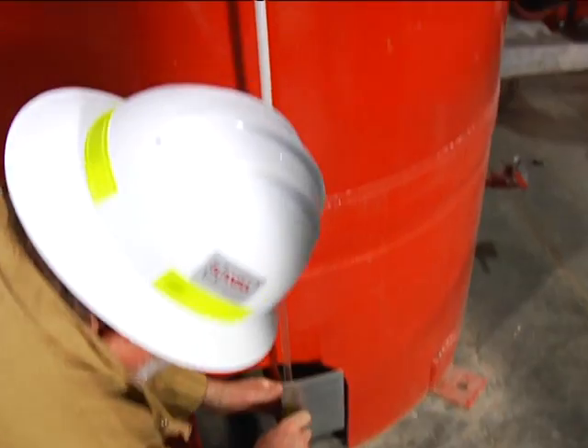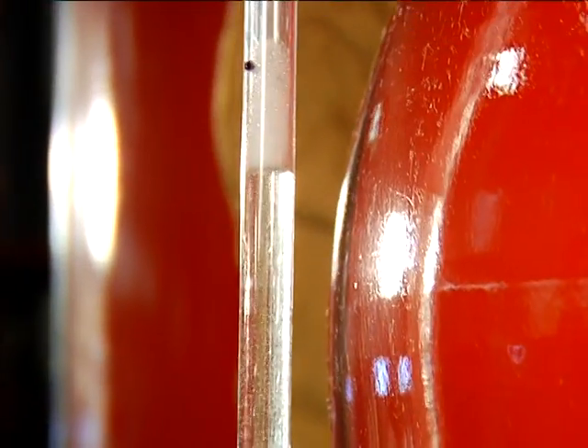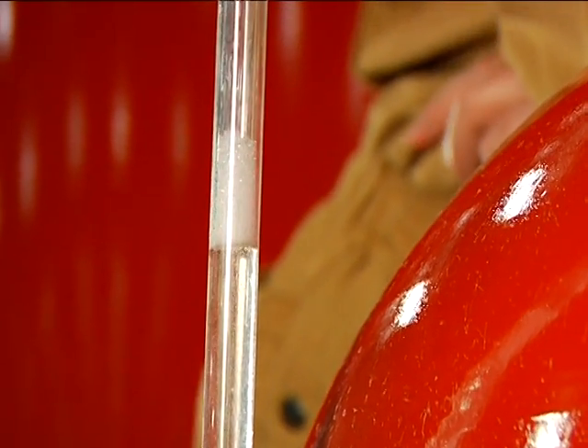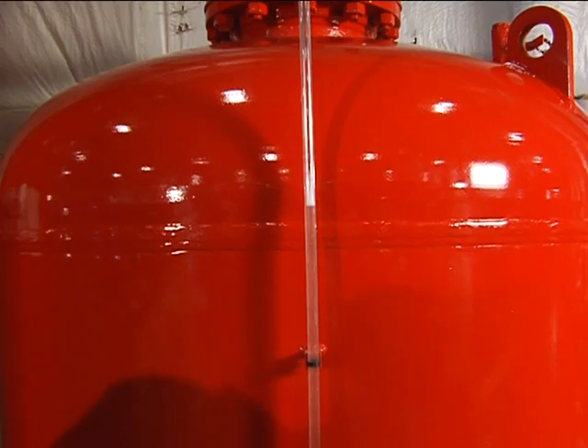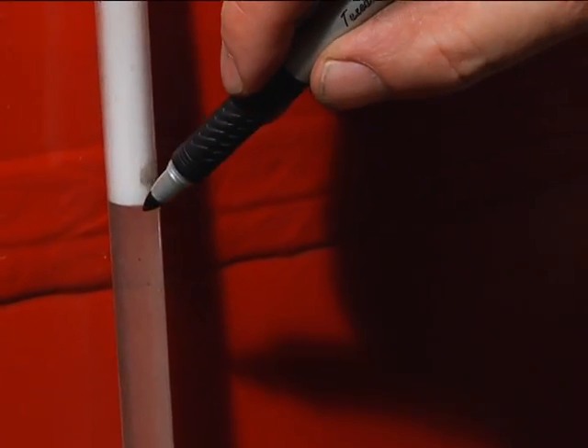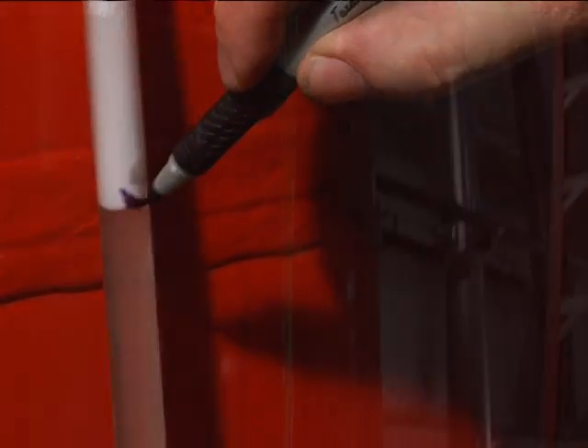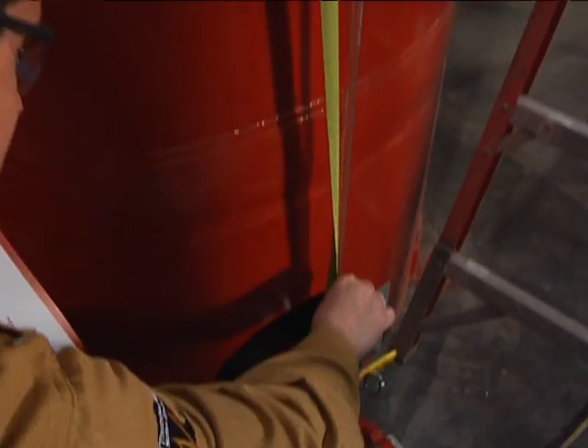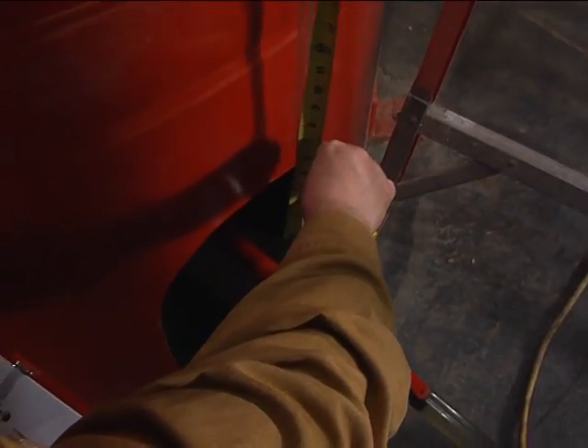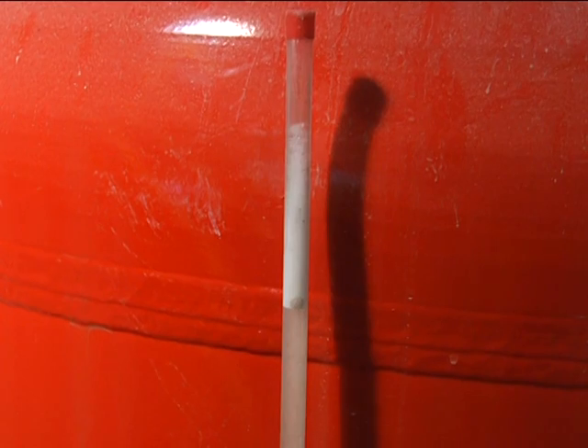Pull the ring pin and turn the sight gauge valve handle to the read position. Allow the concentrate to enter and arrive at a stable level in the sight gauge tube. Next, you'll need to measure and record the concentrate depth in the sight gauge tube. The measurement must be taken from the tube connector at the top of the valve body to the concentrate level in the sight gauge tube shown here.